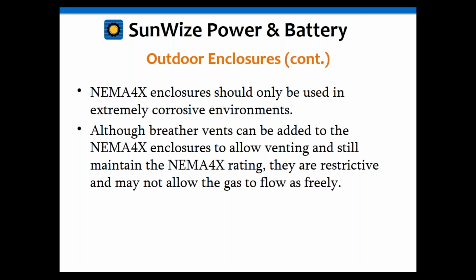A lot of times there has to be a pressure buildup for vents to activate, depending on the type of vents being used. Because of that, there can still be a minor buildup of gas. Nonetheless, we typically recommend you just go with the 3R enclosure if you can. If you're in a situation where you don't have a choice, breather vents can be added, but keep in mind that adds additional cost to the system. If you can avoid it, that's usually the better thing to do.